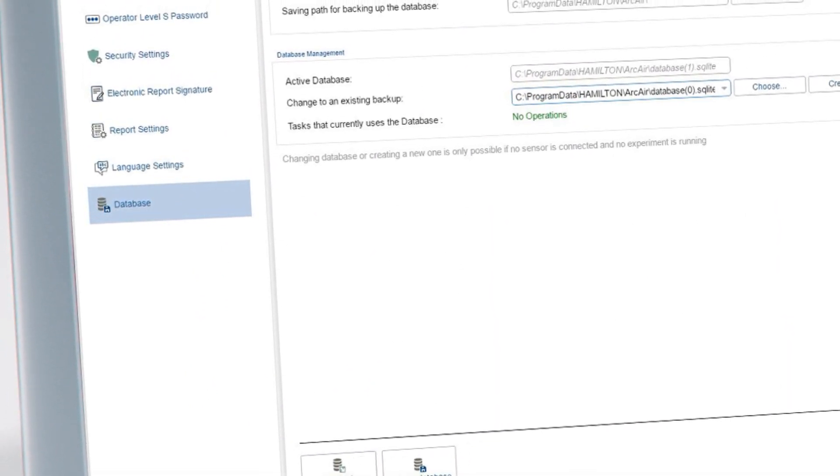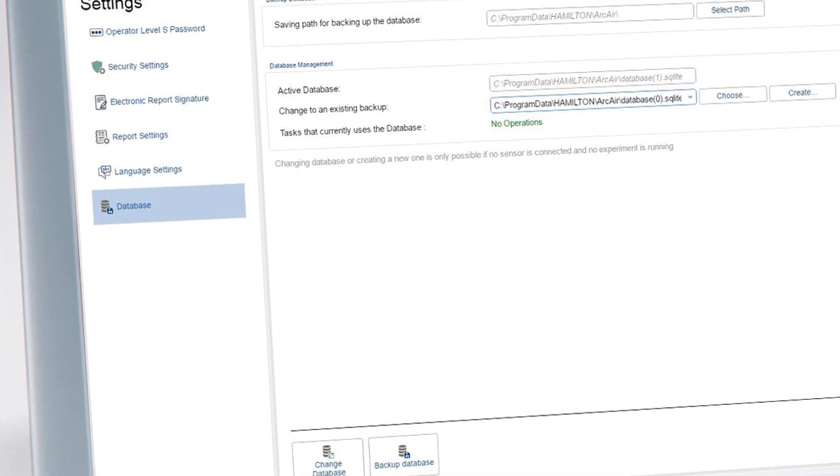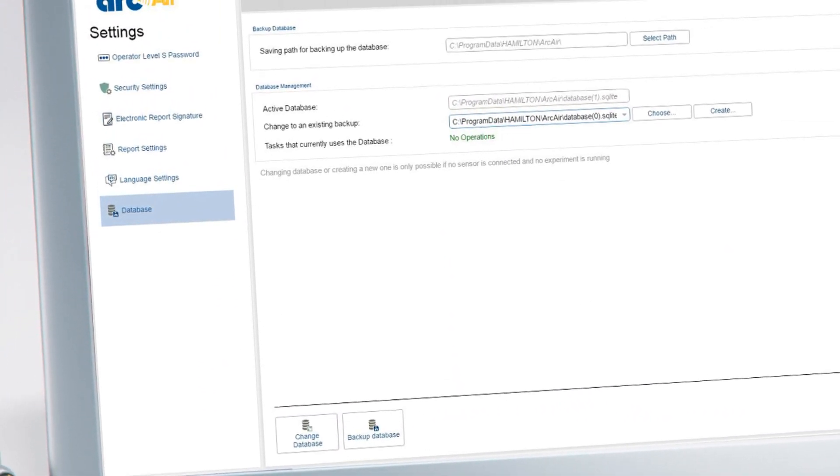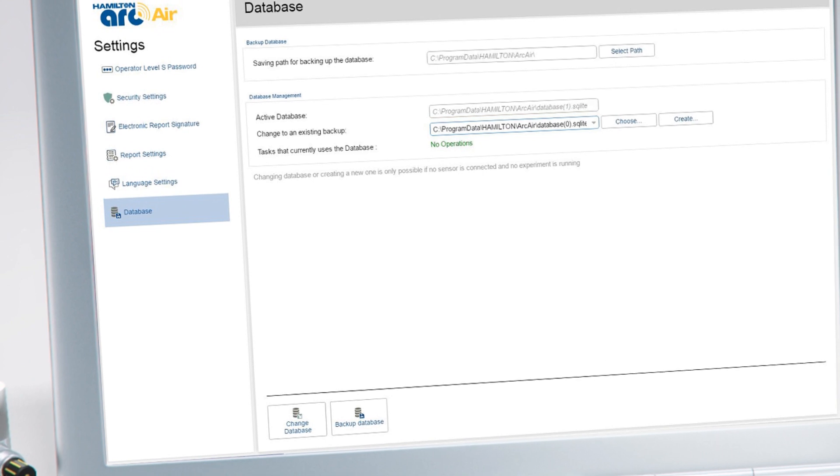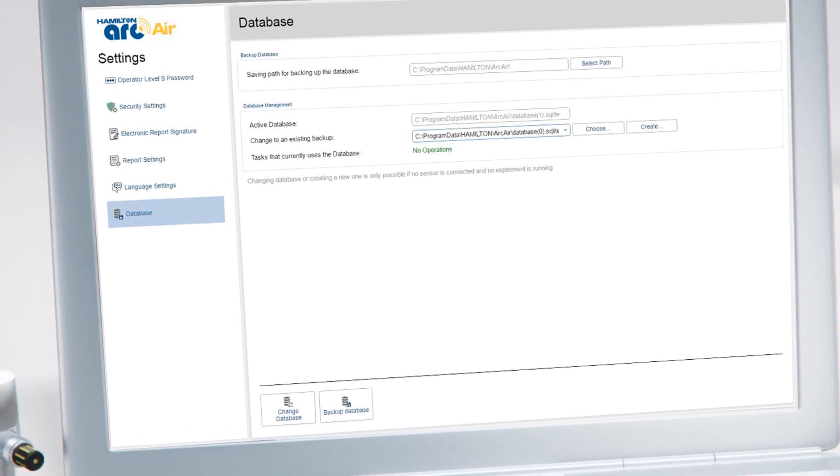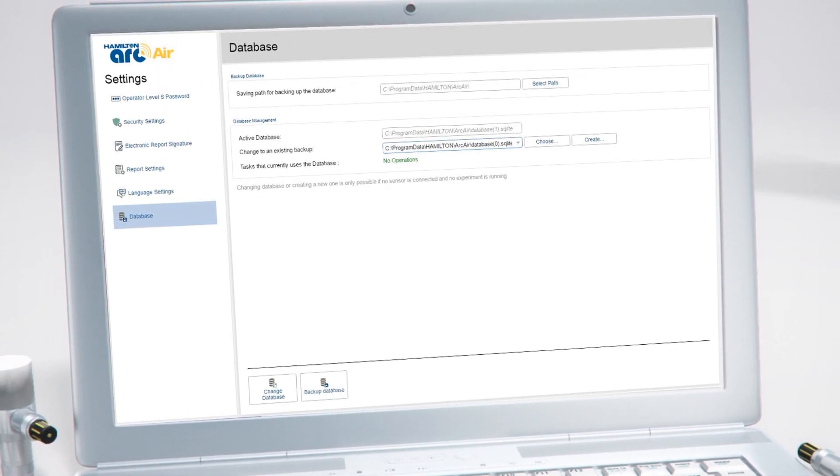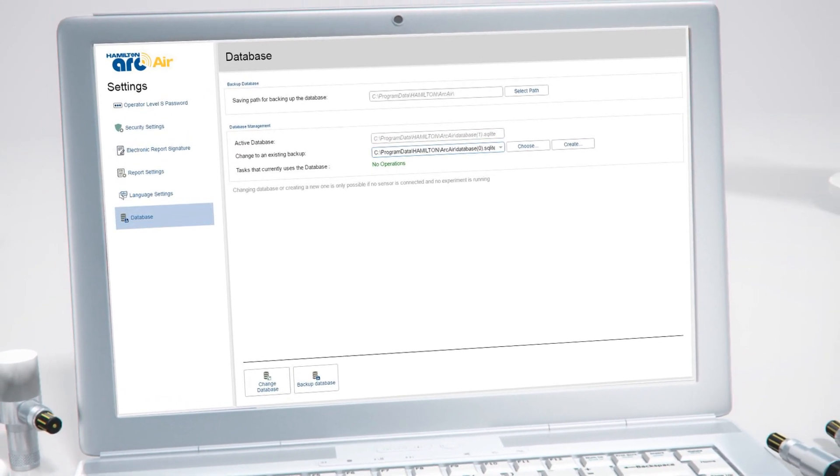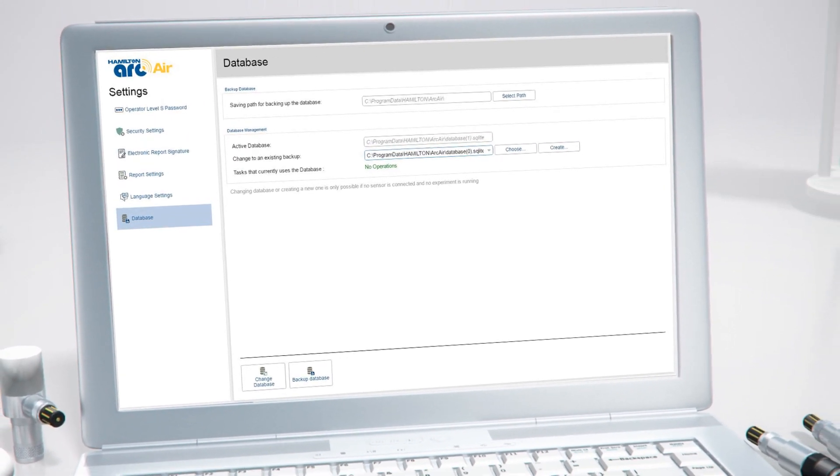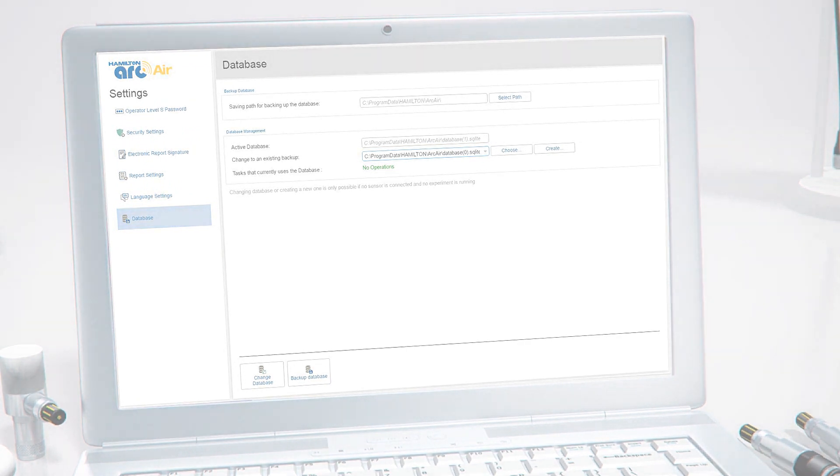Administrators can manage the database, performing operations such as database backup or database restore to older backups. They can change the path where the database is saved as well and customize security settings such as password length and complexity, password expiration time, and user's automatic logout time.